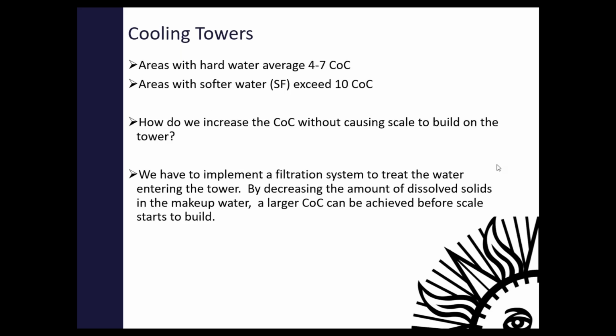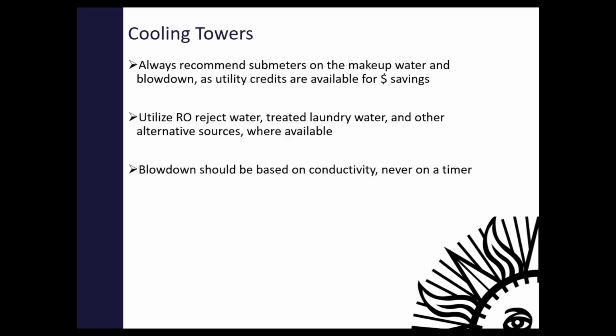So how do we increase the cycles of concentration without impacting our cooling tower? Really, it comes down to filtration and water treatment. If you really want to increase cycles of concentration and where you have hard water, install a water softener. Just a water softener alone can probably get you up to 8 cycles of concentration, in addition to your typical water treatment, of course.